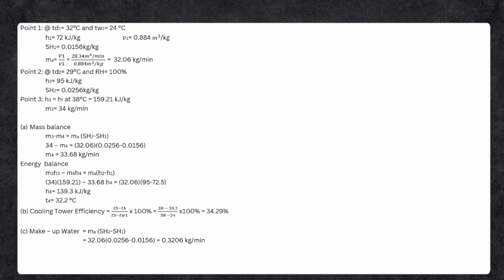And dito naman tayo sa mass balance. M3 minus M4 is equals to MA multiplied by SH2 minus SH1. So, meron tayong 34 kg per minute minus M4 is equals to 32.06 kg per minute multiplied by 0.0256 kg per kilogram minus 0.0156 kg per kilogram. And ang makuha nating M4 is equals to 33.68 kg per minute.